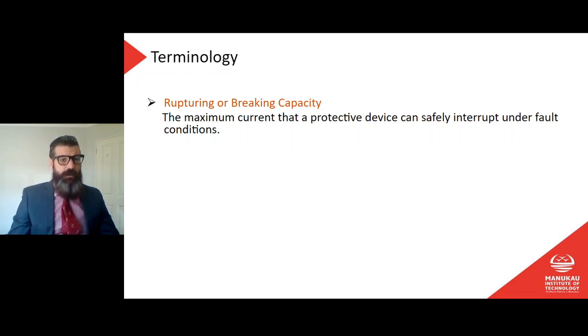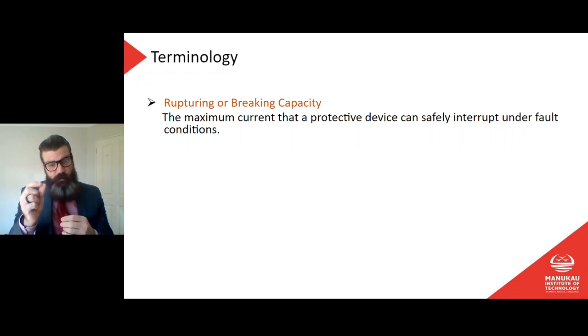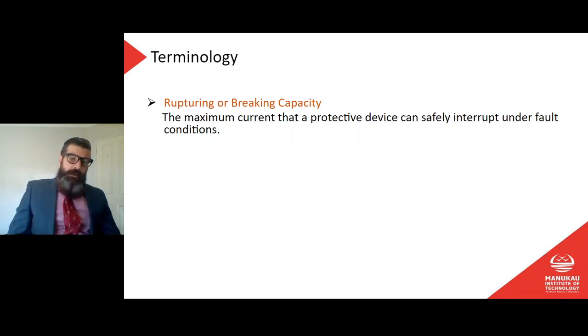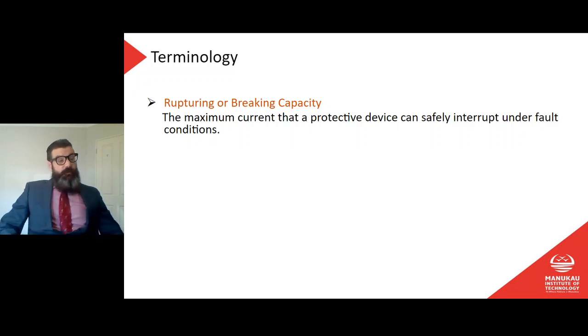If you are in a situation where you need higher, then you go up to 10,000. I presume there's higher ones than that, but I don't think I've ever come across them. At some point you'd probably go to an HRC fuse, because an HRC fuse is always going to have a greater breaking capacity than a circuit breaker, because there's no moving parts that have to separate. It'll just blow. It just blows that wire, remember. So in that case, look, we've got no problem. 6,000 amp breaking capacity, 500 amp prospective short circuit current, no problem at all. But it is something that we need to test.